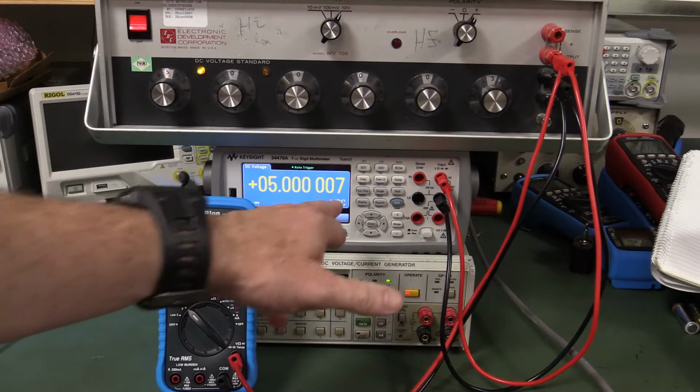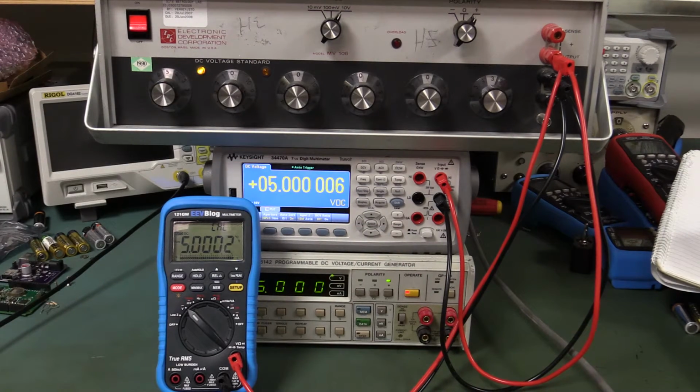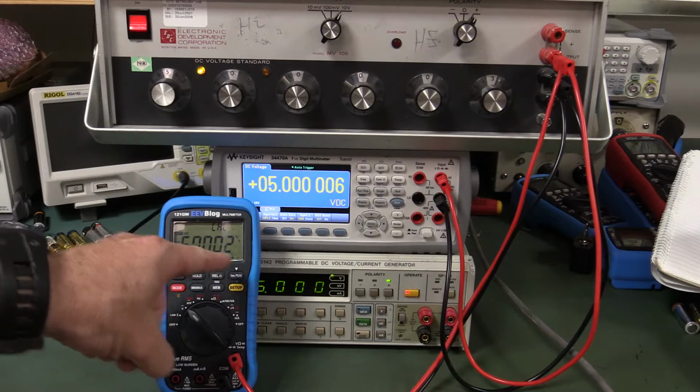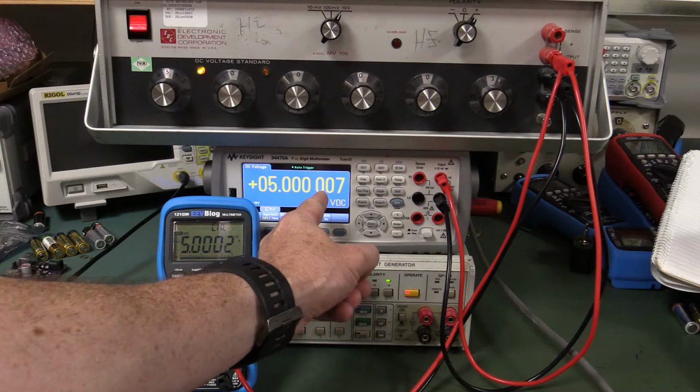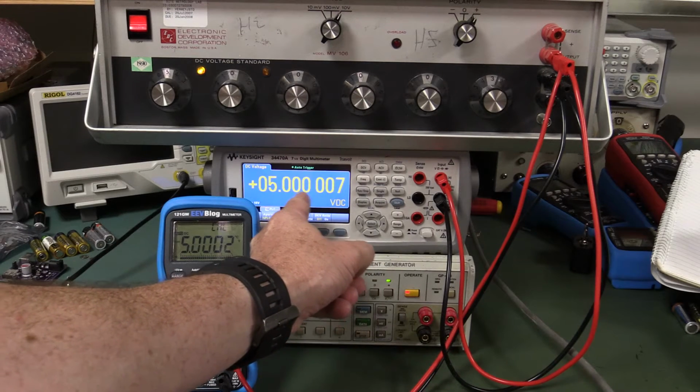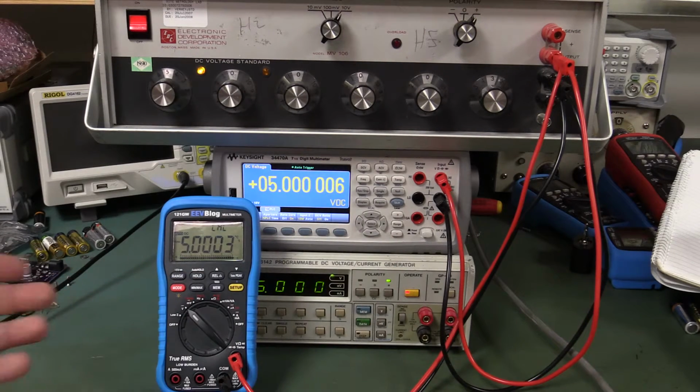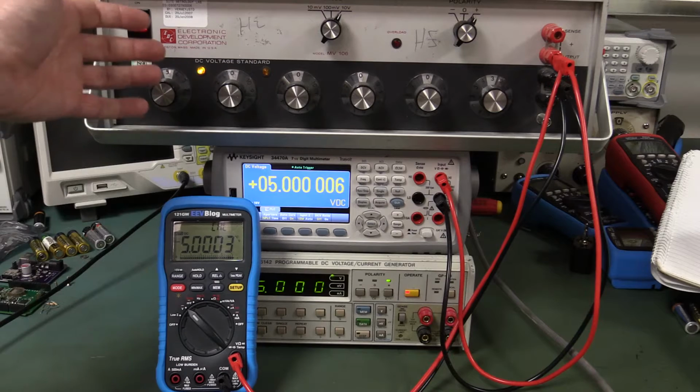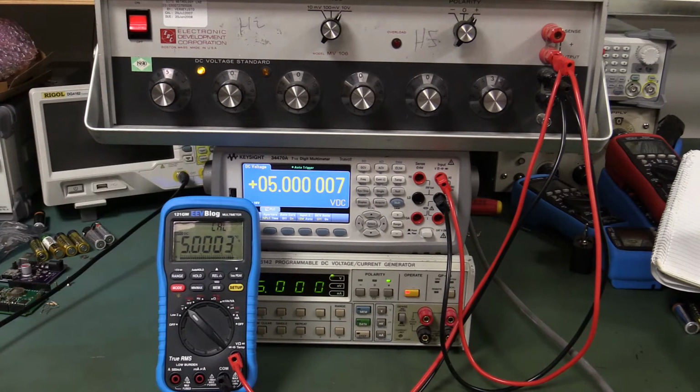Here we go. We're starting, and as you can see, the actual value is not drifting by anywhere near that significant digit here. We're talking about that digit there drifting, 3 zeros and that one. And you can see that the voltage we're feeding in is not drifting at all, because this is a proper decent calibration standard. It's been verified with the Keysight meter, and you can see that it is slowly starting to drift. Once again, not by a huge margin, but it really shouldn't do that because the temperature here is not changing, the conditions aren't changing. So yeah, that is not good.